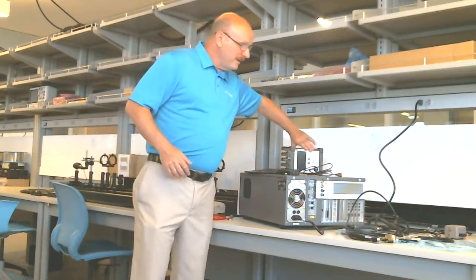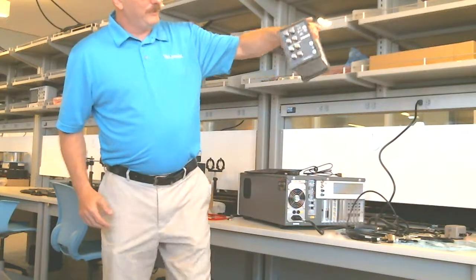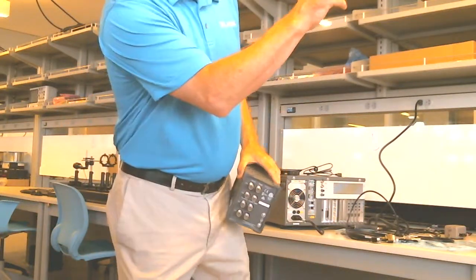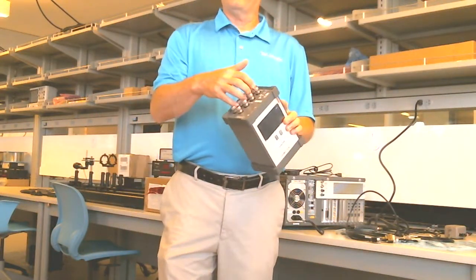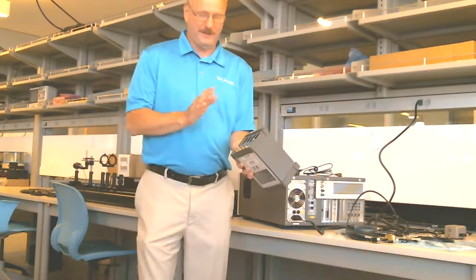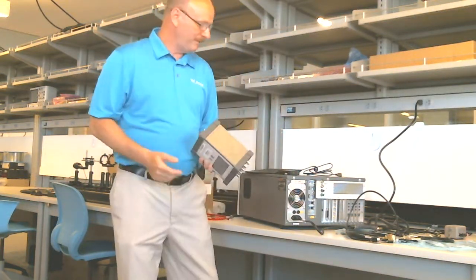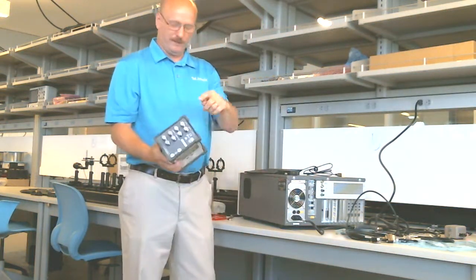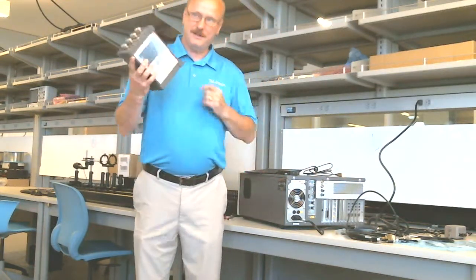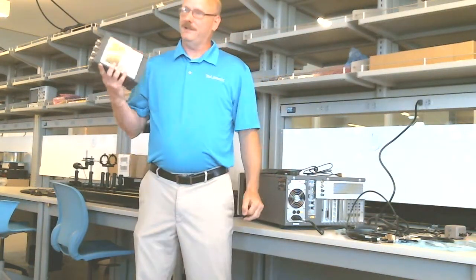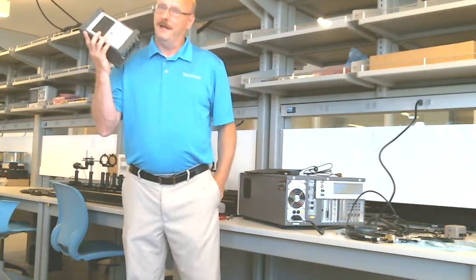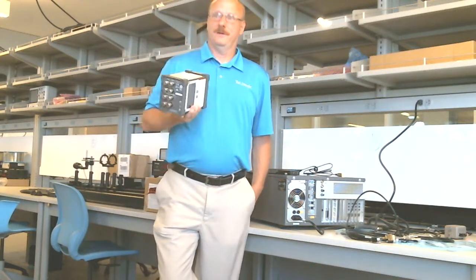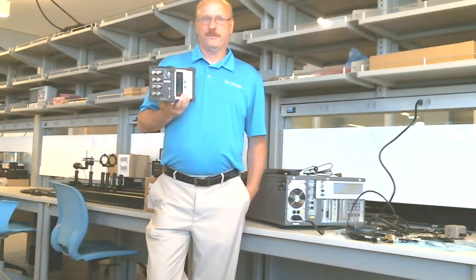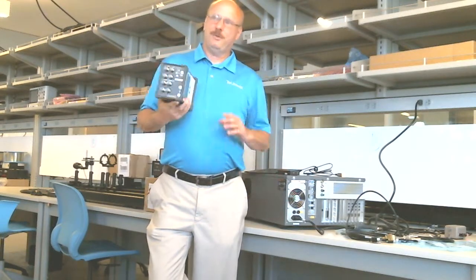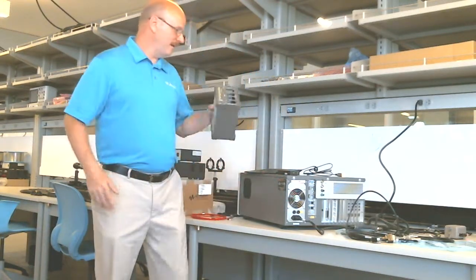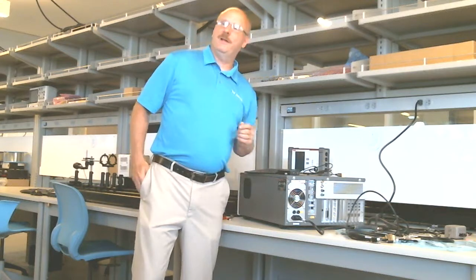You'll put this on your table there as close to your probes as possible. You've got the short cables, you'll run those right to here, and your preamps will be in here. If you don't have preamps, you'll have the pass-throughs that bring them through here. Now, this gives you the ability to switch between CV and DC-IV measurements without lifting probes, which matters because the cabling is different between IV and CV.